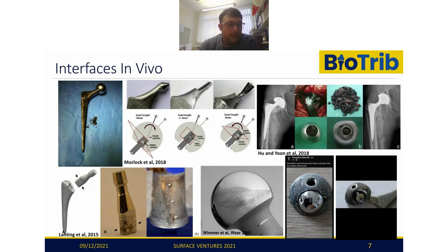So when we take these implants out of the body, they rarely come out looking like brand new as the day that they went in. They tend to come out with these black deposits, evidence of corrosion taking place, degradation on these surfaces, and this can range from blackening of a surface, dulling of a surface, where we see these tribochemical reaction films, maybe the buildup of oxides and the reorientation of some of these surface layers within these fretting crevice corrosions. But it also goes all the way through to where you have gross wear as well. These are very, very rare occasions, but again, they do happen.